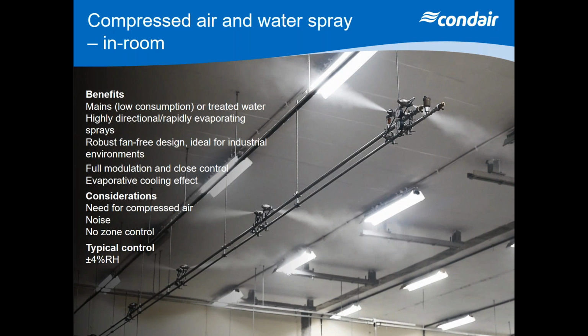Very simply, it's taking a compressed air and water supply, modulating it and taking it through lines and then attaching a nozzle to those lines, and inside the nozzle the compressed air and the water is mixed together. We get a very fine spray going into the space. And here we would consider the nozzle size and the height of the mounting of the nozzles as to where we would mount the lines. Again, the limiting factor is there's no zonal control. So one area will work from one humidity stat or sensor. If you want zonal control, you have to go to a high pressure system.